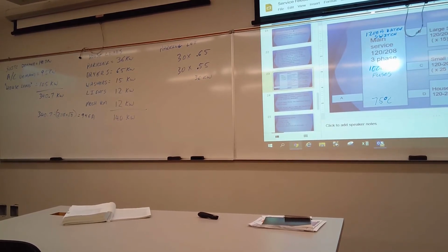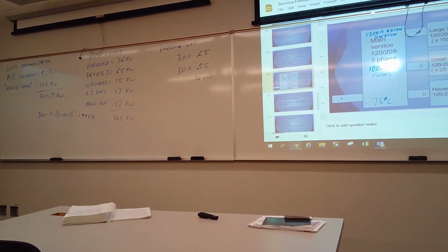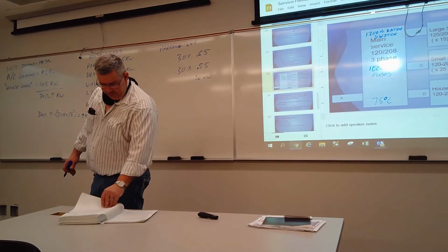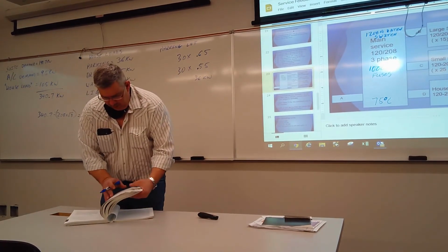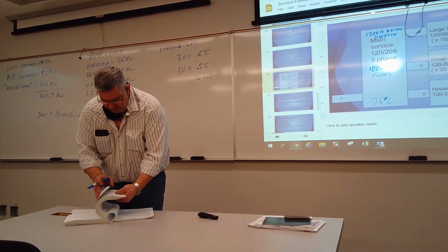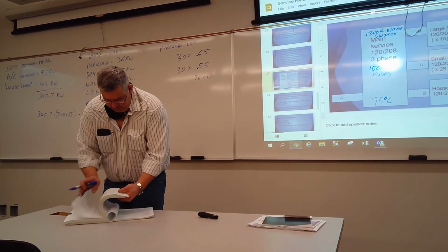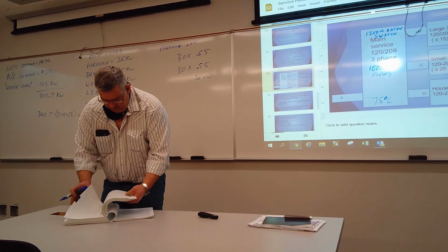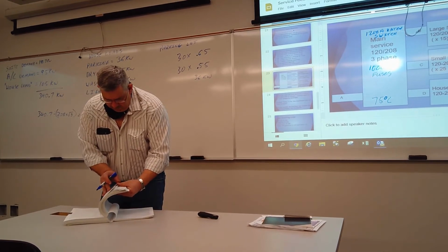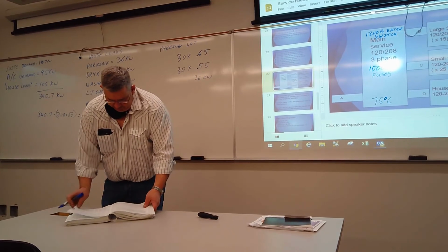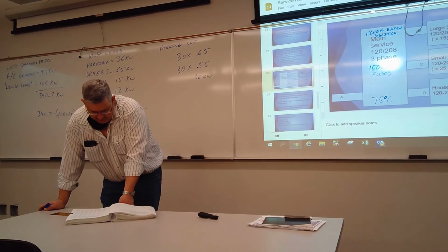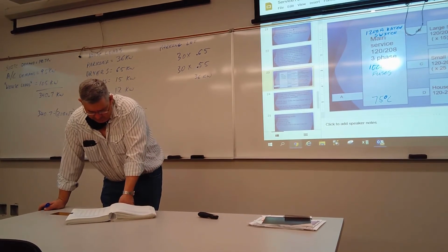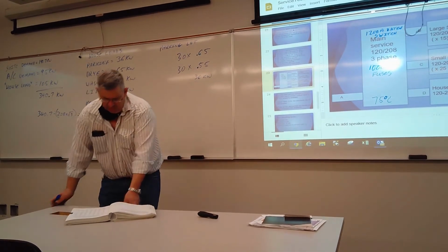aluminum conductors, what's our best option to get 946 amps worth of ampacity at 75 degrees? Any opinions, thoughts? That'd be 15 units. You'd have to use at least 1250s, but I think you have to do the derating. Do you want to use 1250s?